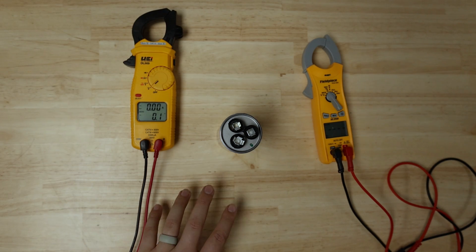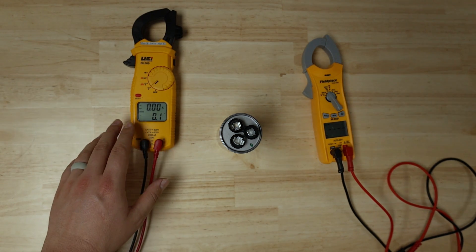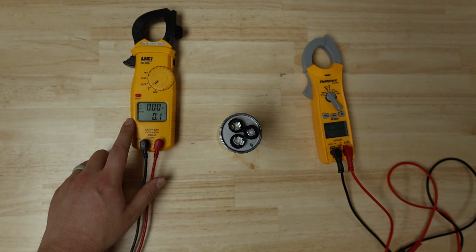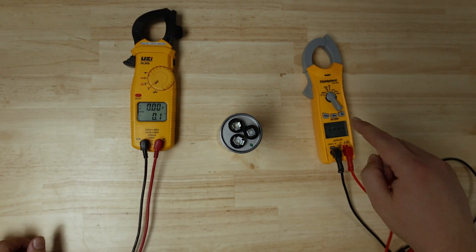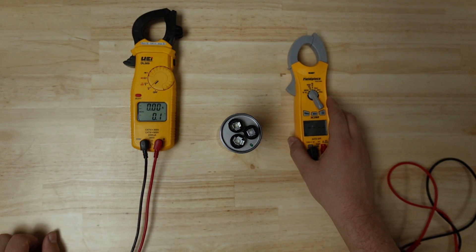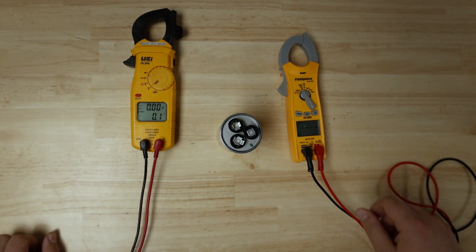We also want to do microfarad readings with these meters. It should be noted, though, that this model of UEI meter does not actually measure microfarads. The Fieldpiece, however, does. If you set it to MFD, which is the same symbol for ohms, you'll be able to measure your capacitor.